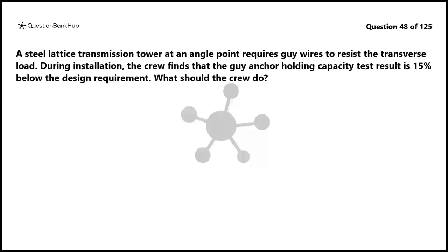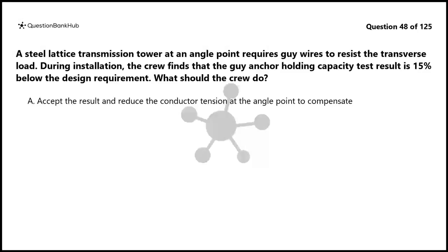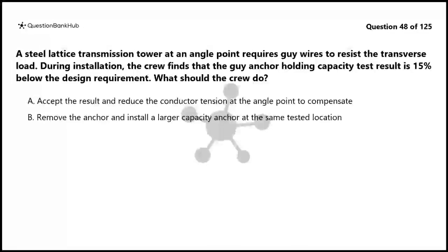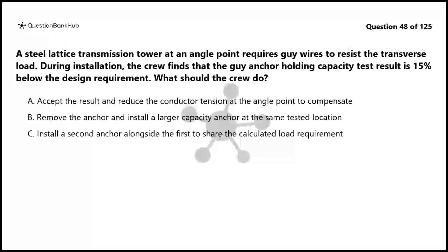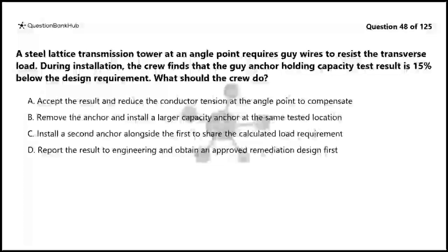Question 48. A steel lattice transmission tower at an angle point requires guy wires to resist the transverse load. During installation, the crew finds that the guy anchor holding capacity test result is 15% below the design requirement. What should the crew do? A. Accept the result and reduce the conductor tension at the angle point to compensate. B. Remove the anchor and install a larger capacity anchor at the same tested location. C. Install a second anchor alongside the first to share the calculated load requirement. D. Report the result to engineering and obtain an approved remediation design first.